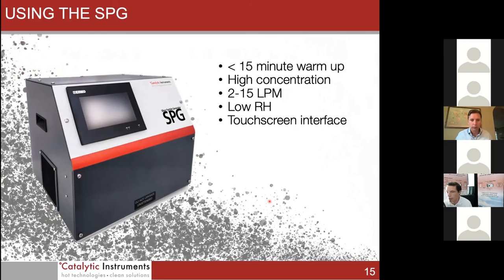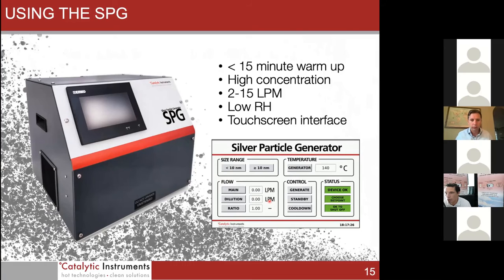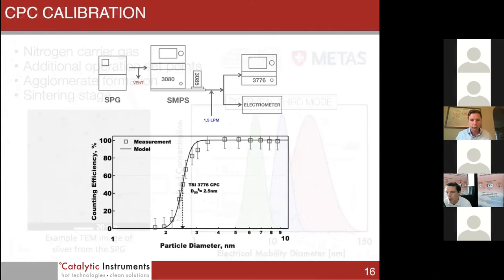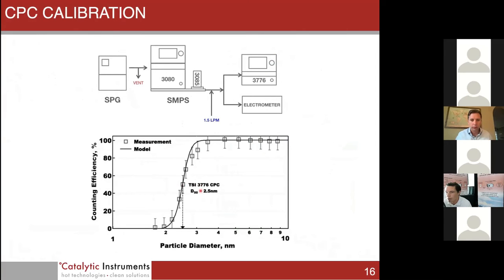Using the SPG, it has less than 15 minute warm-up time and can be operational within half an hour or so. High concentration, 2 to 15 liters per minute outflow, very low RH less than 5% on the output, and is operated by a touchscreen interface. Here's an example of a CPC calibration. It's relatively simple - you go backwards and forwards across different particle diameters to derive this sigmoid curve, figuring out what your D50 cut of your CPC is. Our CPC was pretty much within calibration spec, so that's one application of the SPG.